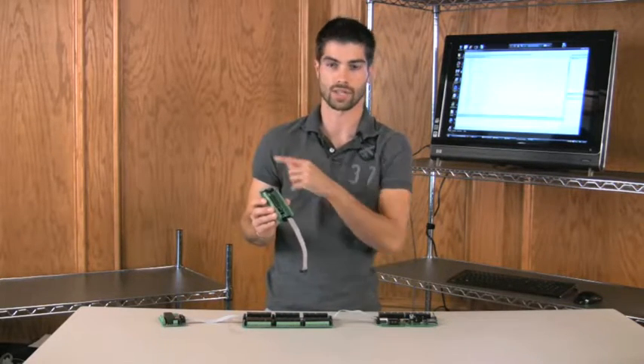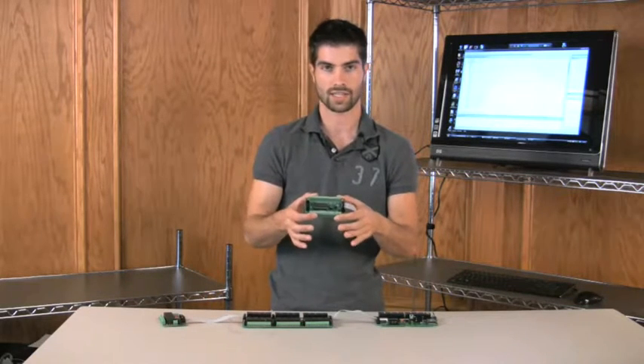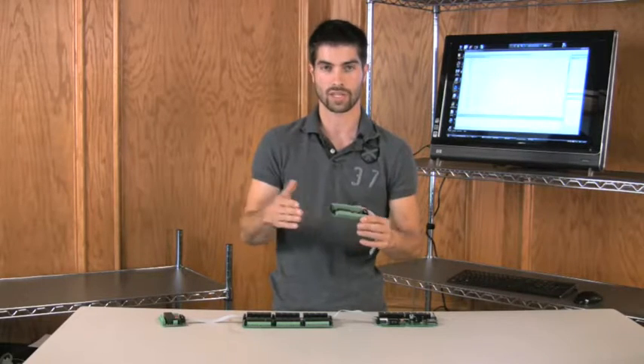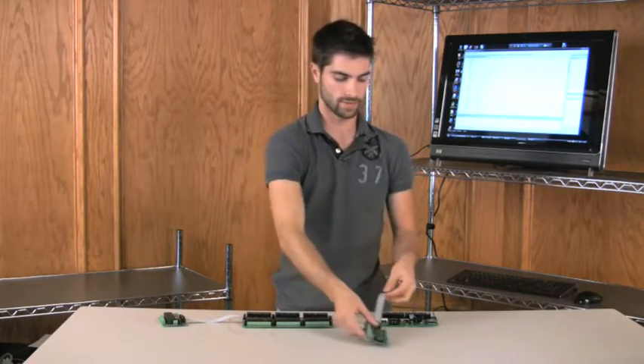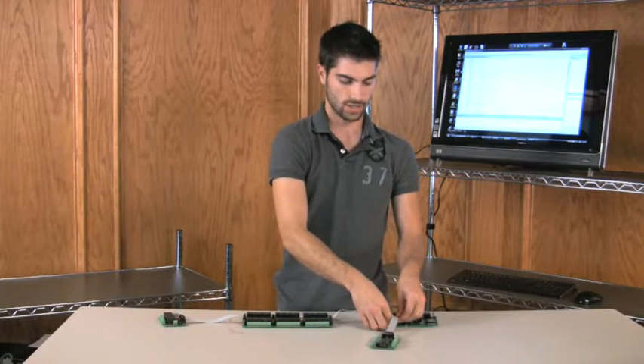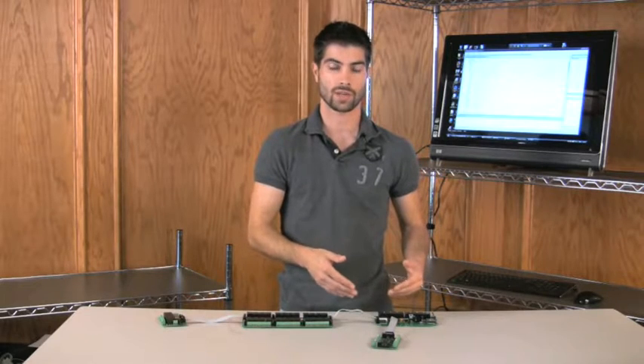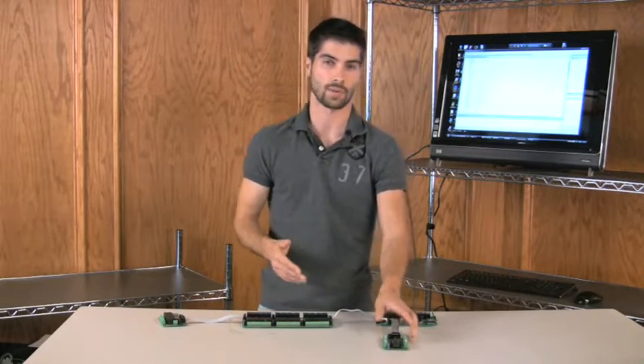So I can add a whole bunch of these up to 256 channels. This one here has 16, so I can add an additional 16 boards, giving me up to 256 channels. And it comes with a ribbon cable and I simply attach that to the UXP expansion port. You'll have to make sure that the controller you purchase has a UXP expansion port on it if you plan on adding things to that port.